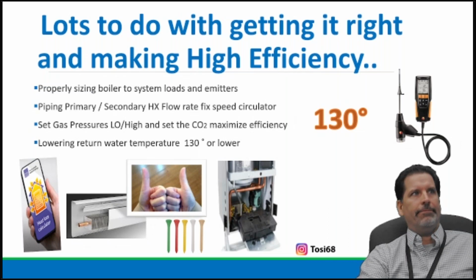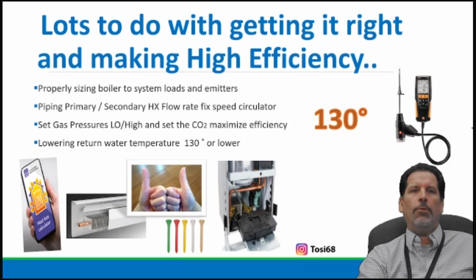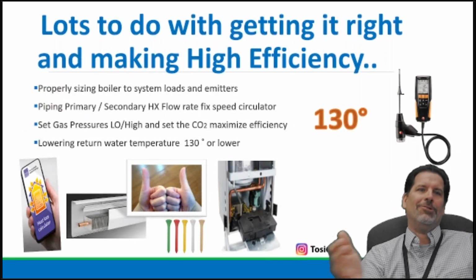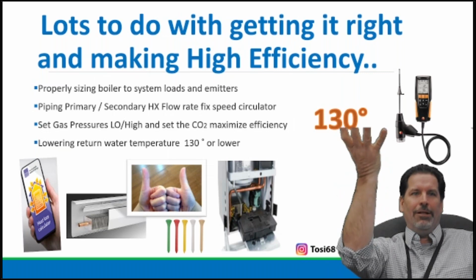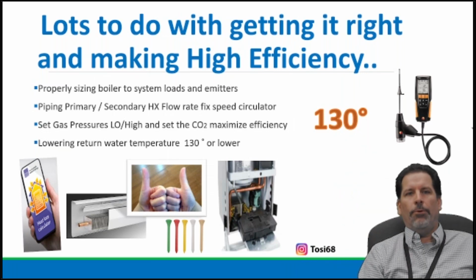I have homes on the east end of Long Island, they're basically like hotels, right? Before COVID, they were very seasonal residential homes. Some of these homes have 15, 17 bathrooms in them, and it's all about domestic hot water. And they use large indirect storage tanks off of large BTU boilers. I compare the home's heat loss and the domestic load. I mean, that's why the boiler is so big.